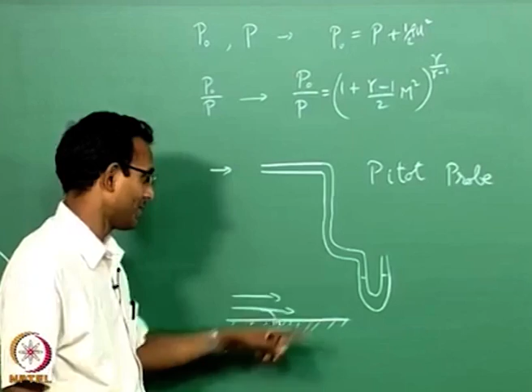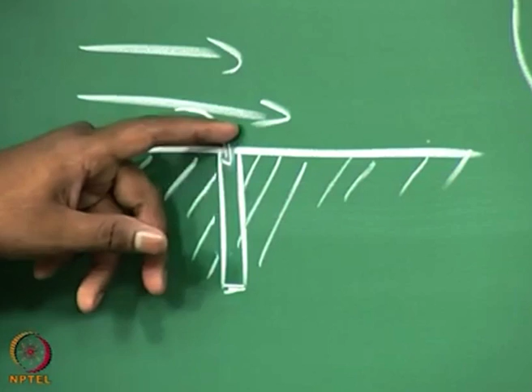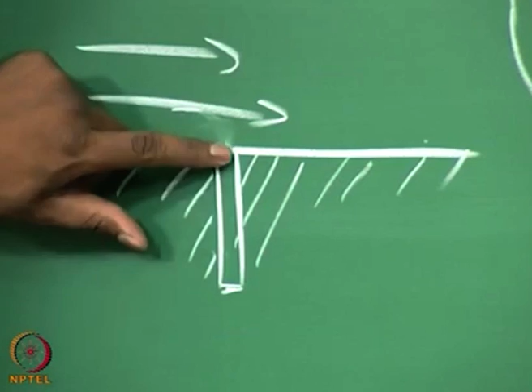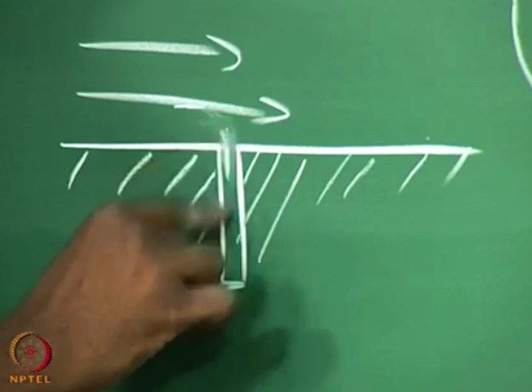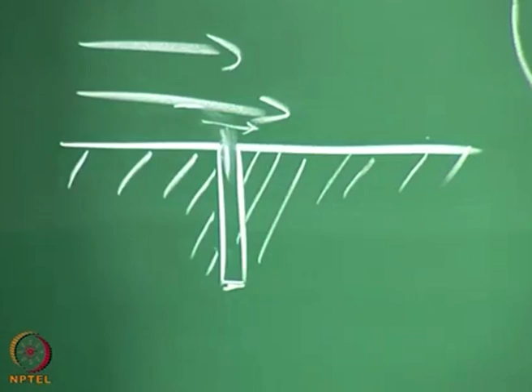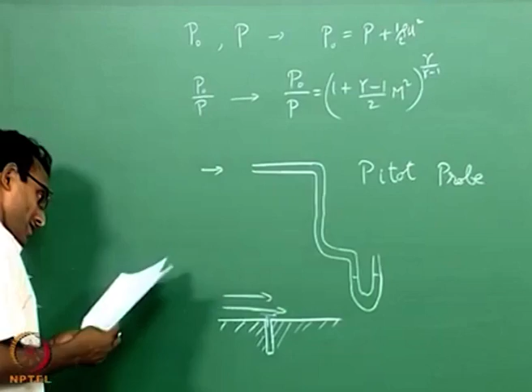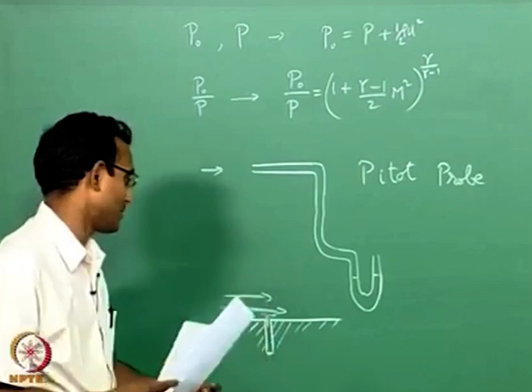Again the same thing as here, if I put a pressure device there, say a pressure transducer, then that is going to be sitting somewhere here, that will stop the flow, but this system will come to equilibrium when this pressure is the same as this pressure, and after that the streamlines will just be going straight. Okay. That is what will happen here. If this is the case, then I am actually measuring the pressure at this location, at that entry of the port, and then at that point I am going to say I am measuring pressure in that particular pressure port, and it is going to give you the static value. Why? It is not pushing anymore on the sides, it is not turning into the flow. Okay. This is the typical method. This is the wall tapping. Okay, I am tapping from the wall to measure the pressure.